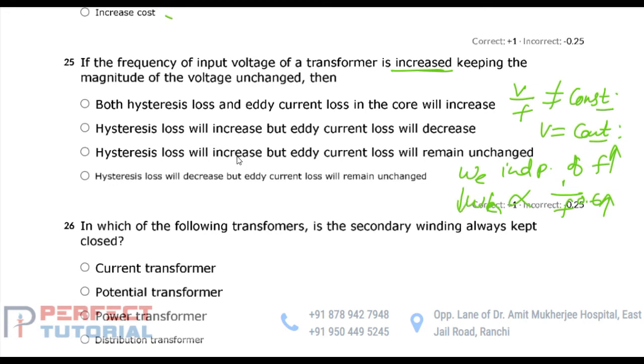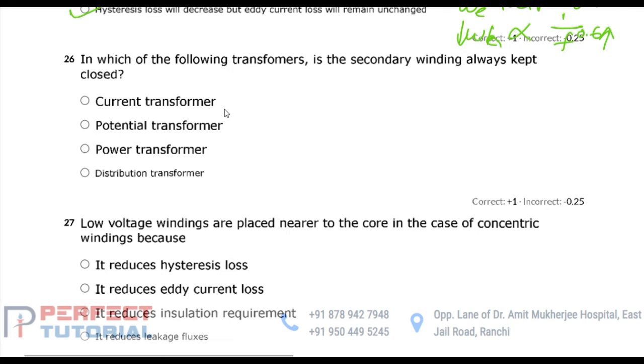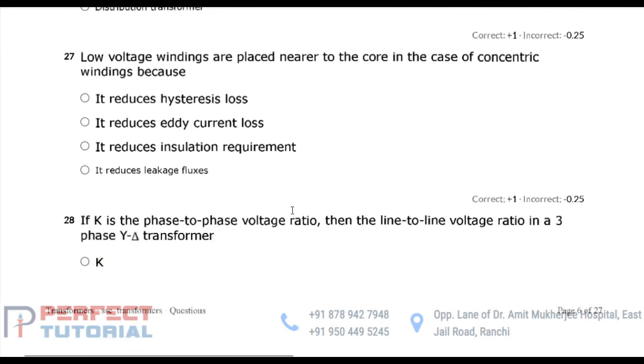So this would be correct answer here. Next, in the following transformer, the secondary winding always kept closed. Say it is required in current transformer. Okay, low voltage winding are placed nearer to core in case of concentric winding because देखिए particularly in case of core type core based transformer, LV winding is placed nearer to the core and by doing so you can reduce the amount of leakage flux. You can increase the amount of linkage flux and hence can increase the power transfer capability of transformer. Also it reduces the volume of insulation material required. That is a major advantage of using or of placing LV winding nearer to the core and HV winding farther from the core. So one of the option you see please, it reduces the insulation requirements.